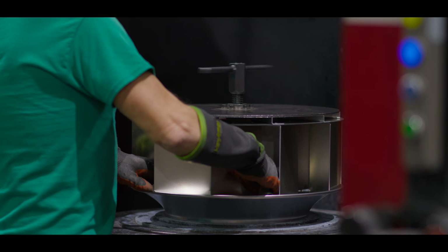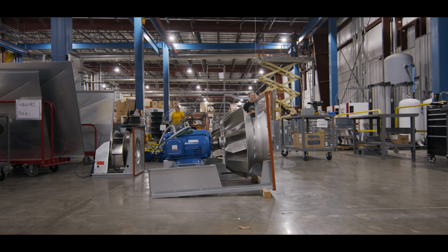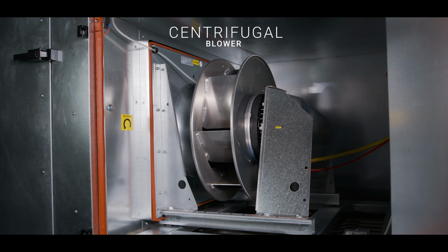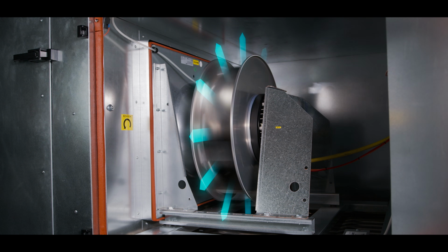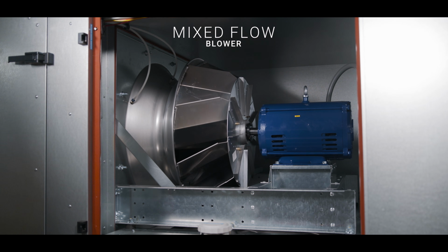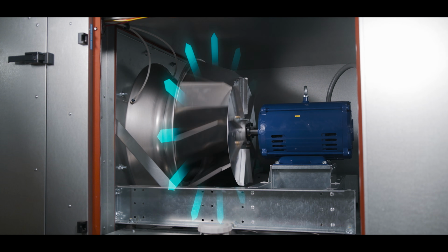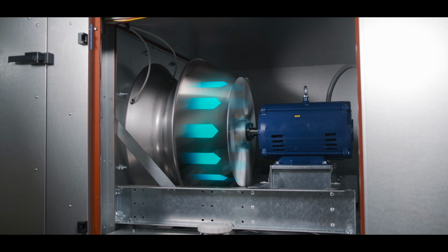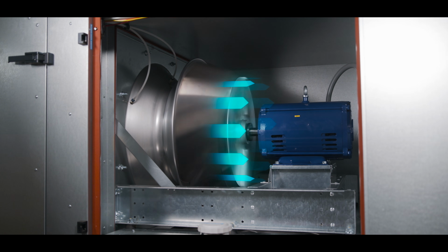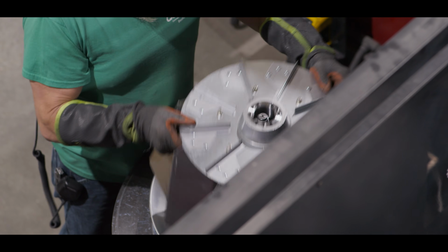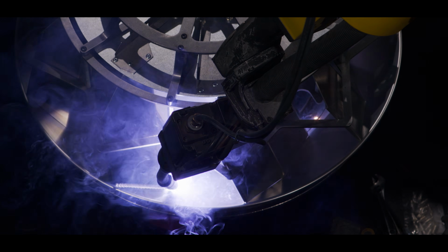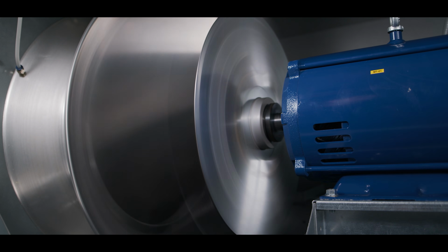Motor selection also depends on what type of fan we're using, and we can specify two designs. The first is centrifugal, meaning as the fan spins, the air is forced centrifugally around the fan. These fans are simple, affordable, and excellent at overcoming static pressure. The second is a mixed flow design. So what are we mixing? Well, a mixed flow wheel is part centrifugal and part axial, also forcing air longitudinally across the fan. Adding the axial element helps improve efficiency when moving high volumes of air. It also allows us to manufacture a more structurally robust wheel that we can spin faster and with less vibration. Thus, our mixed flow wheels can handle even higher static pressures.